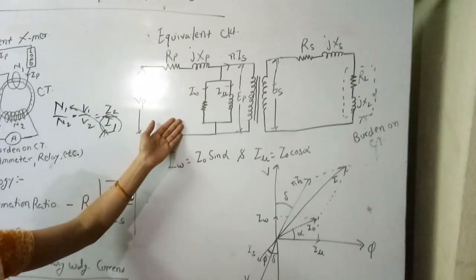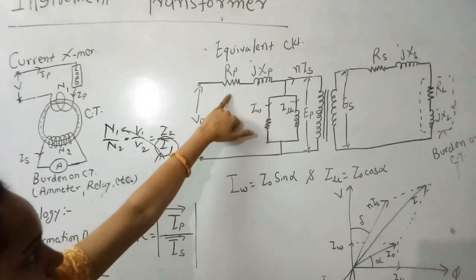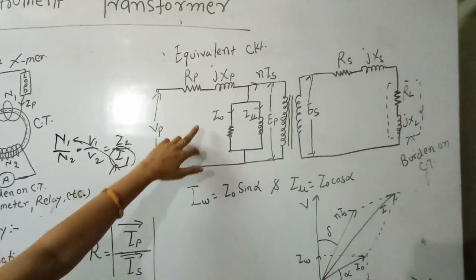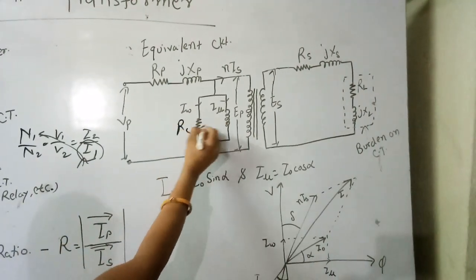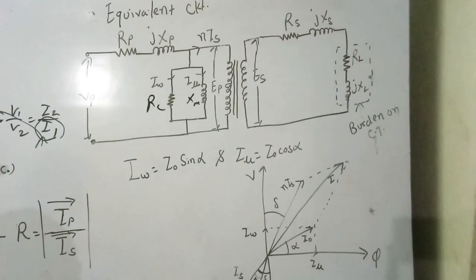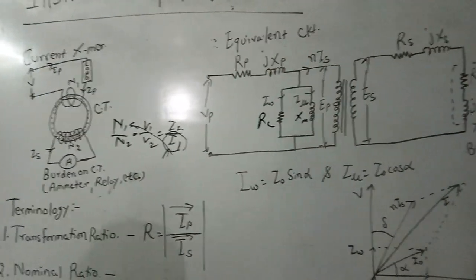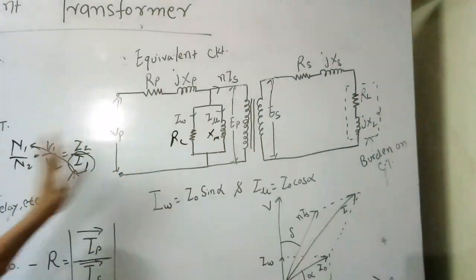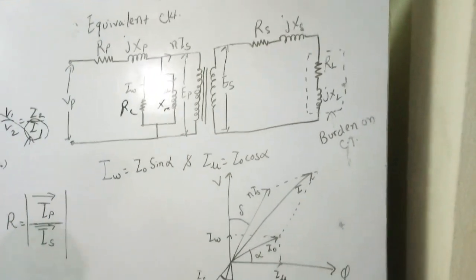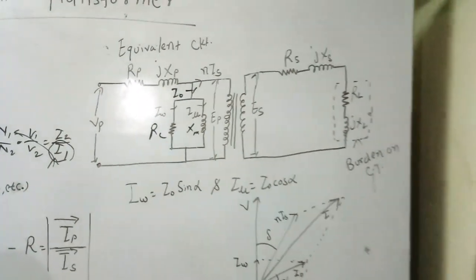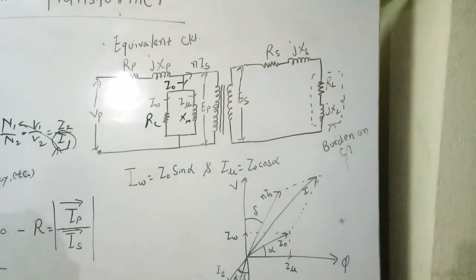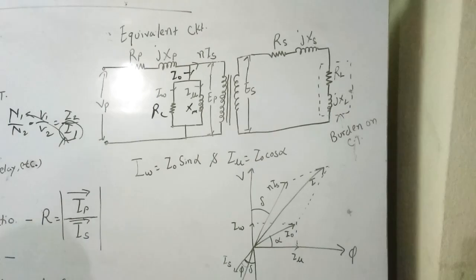Now we come to the equivalent circuit of the CT. It has a primary combination of resistance and inductance, a parallel combination of core parameters RC and XM, and a secondary equivalent circuit with secondary resistance and secondary inductance. The burden on the CT measures current. The no-load or exciting current produces the magnetic flux, following the basic principles of the transformer which are also applicable for CT.